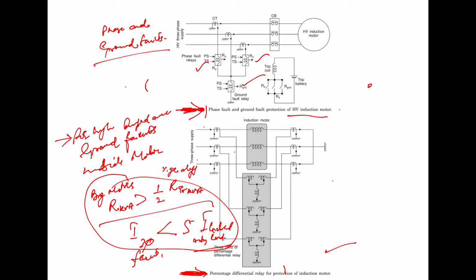Percentage differential protection, as shown here. It is similar to whatever we have used in the other cases also in the transformer. However, if the motor kVA rating is less than half of the supply transformer kVA rating, definitely we are going for the overcurrent relay.